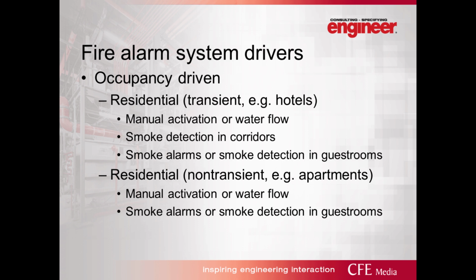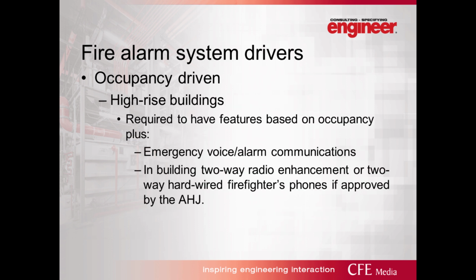But one of the biggest differences is that within a transient residential, smoke detection is required within the corridors of those occupancies, whereas in an apartment building, corridor smoke detection is not required. So in a high-rise building or a multi-story building where you have elevators, you're going to have at least one smoke detector in the elevator lobby. That's usually adjacent to the corridor, but otherwise the corridor itself is not required to be protected.